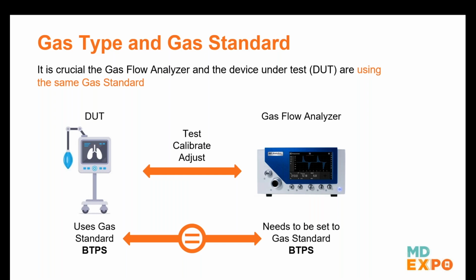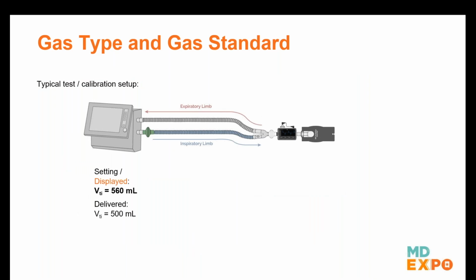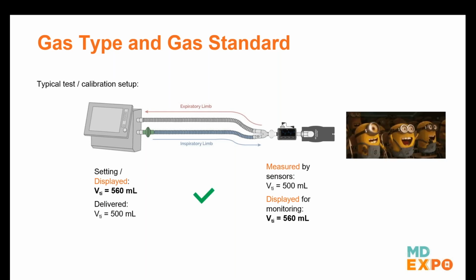It's not always easy to tell what the units are being displayed on a ventilator. Sometimes you have to dig a little deep. You have to go to the ops manual and ask, what does this unit display in? Is it ATP, STP, one of the other 17 gas standards, or is it BTPS? And then you set your analyzer correctly. And now when the ventilator is saying 560, but it's putting out 500, you're measuring the 500, but it's displaying 560. Now you have apples to apples and you're happy. Okay, in this case, it might be bananas. No.